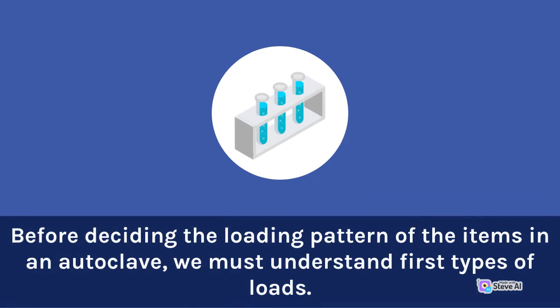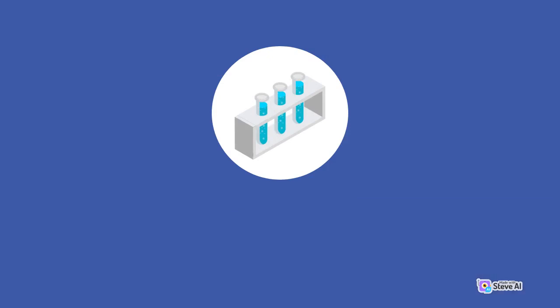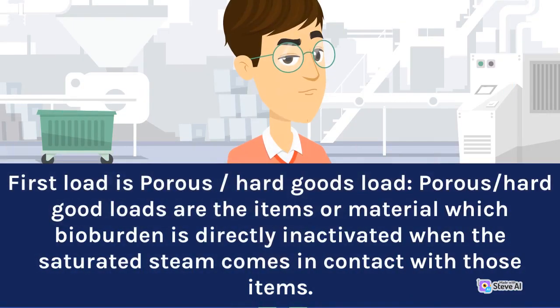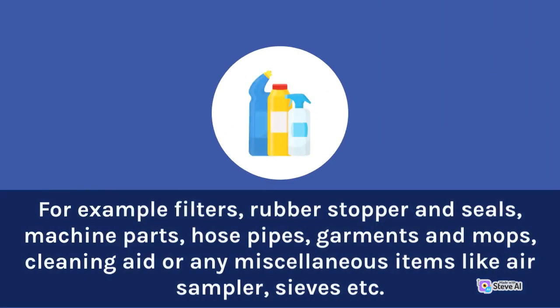Before deciding the loading pattern of the items in an autoclave, we must first understand types of loads. The first load is porous/hard goods load. Porous/hard goods loads are items or materials whose bio-burden is directly inactivated when the saturated steam comes in contact with those items. For example: filters, rubber stoppers and seals, machine parts, hose pipes, garments and mops, cleaning aids, or any miscellaneous items like air samplers, sieves, etc.